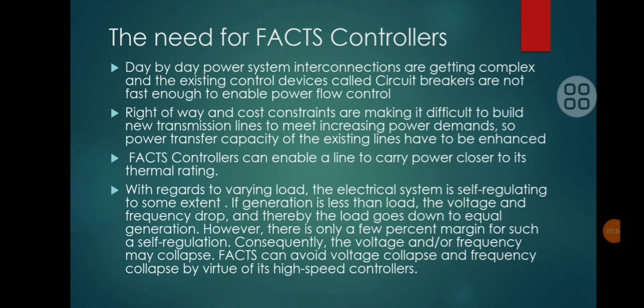Also, every power system has a self regulation. Generation always should balance the load. If generation is less than the load, the voltage and frequency drop, and thereby the load goes down to equal generation again. This is called self regulation. However, there is only a few percent margin for such self regulation. Consequently, the voltage or frequency may collapse. FACTS can avoid such issues by virtue of its high speed control.